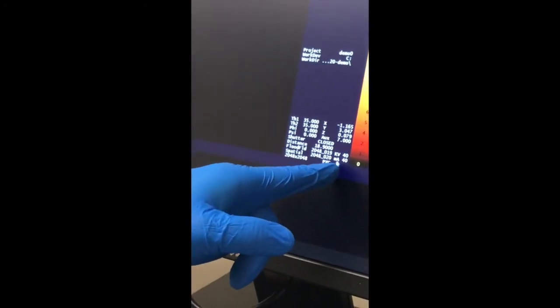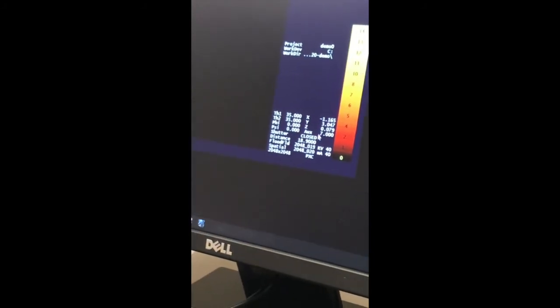We're gonna close this. Next, we go to the program called GADDS, which is next to the D8 Tools, and then double click again. So this will come on. All right, and there are a few things we're gonna check. The first thing I do is to set the generator to user settings, so 40 kV, 40 milliamps. You just say yes. So this will go to 40 kV, 40 milliamps from standby position.